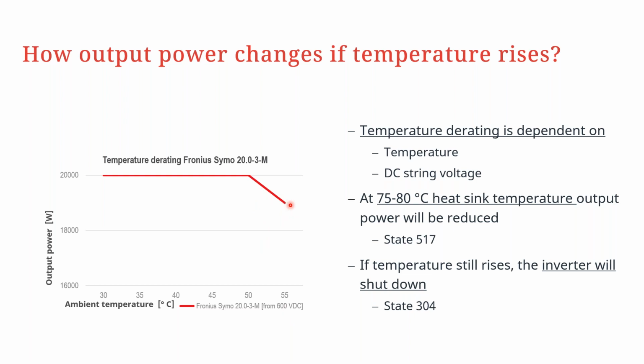In the unfortunate event that the heatsink temperature goes to, let's say, between 75 to 80 degrees Celsius, then the inverter will start derating power output and will send you a state code 517 regarding a high heatsink temperature. If this temperature continues to rise and does not go down from this threshold, then at some point the inverter must stop to protect the electronics, and a state code 304 will then be sent to SolarWeb. But if you are on site, you can also see the various state codes if the inverter has a problem on the display of the Snap inverter.